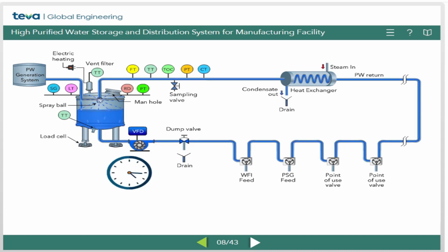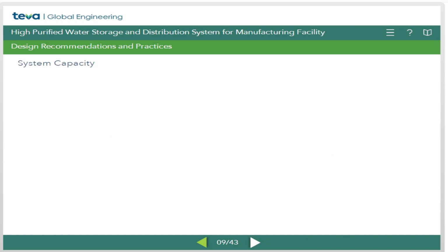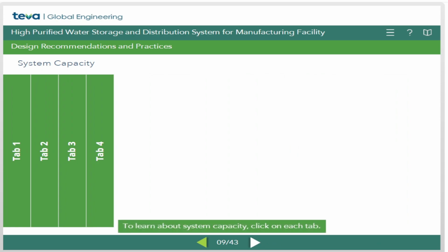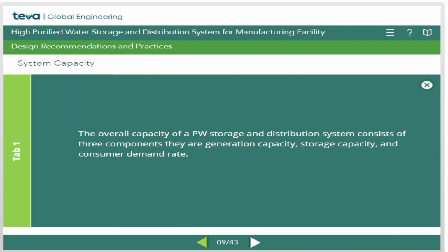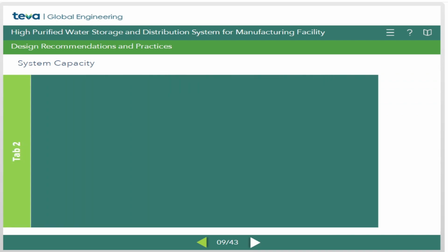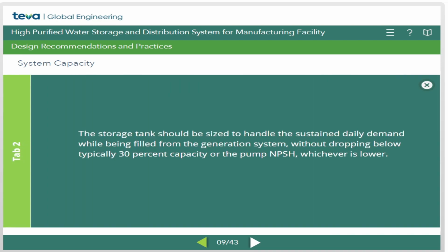The distribution loop should circulate water continuously 24/7 to keep water available for production at any given time and to resist microbiological growth. To learn about system capacity, click on each tab. The overall capacity of a purified water storage and distribution system consists of 3 components. They are generation capacity, storage capacity, and consumer demand rate.